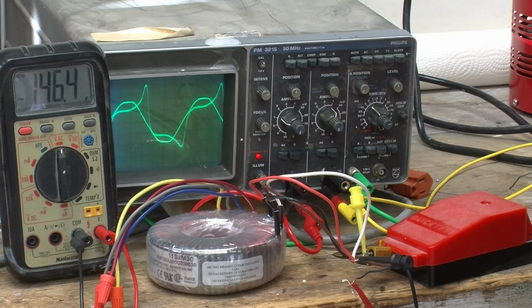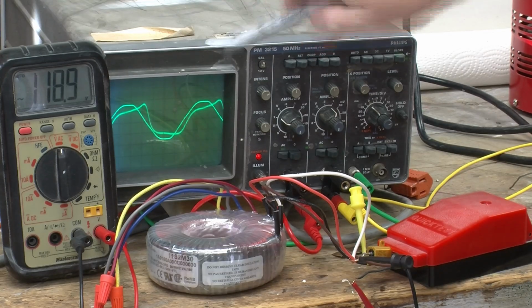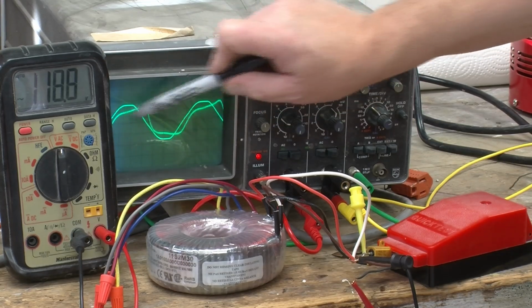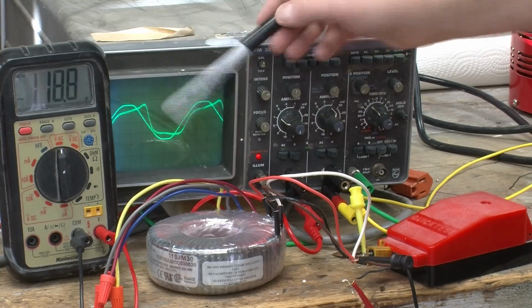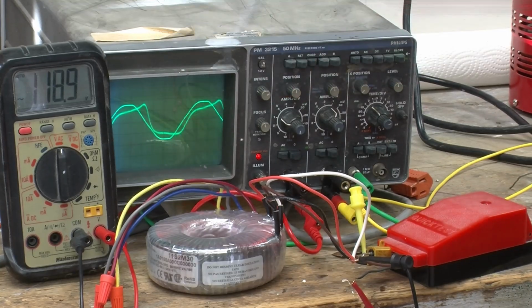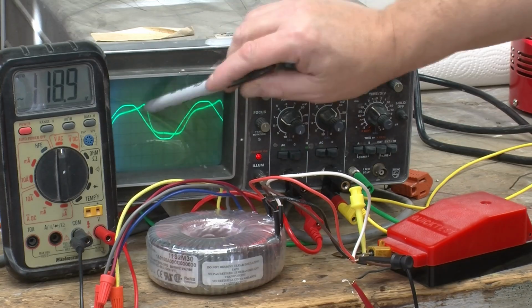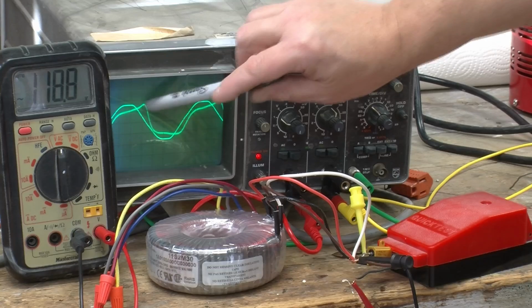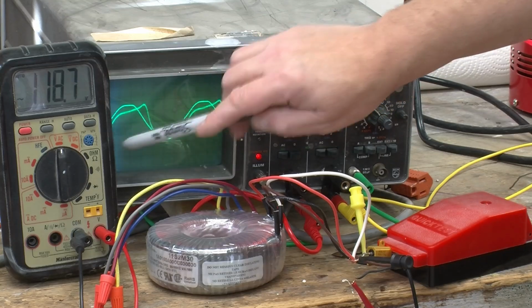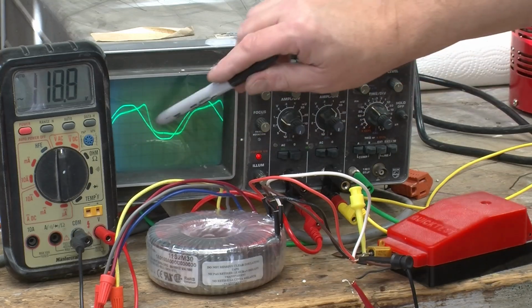Now let's get back to a much nicer zone. Interestingly, if we set the voltage to about 118, 119 volts, the transformer was clearly designed so there's a little peak here — not because they particularly wanted that peak, but because they made a compromise in terms of the size of the core, the number of windings, and so forth. Since this is only somewhere in the 15 milliamp range, that peak doesn't really matter. But if you had a lot of transformers like this, it would be a little hard on the power system.